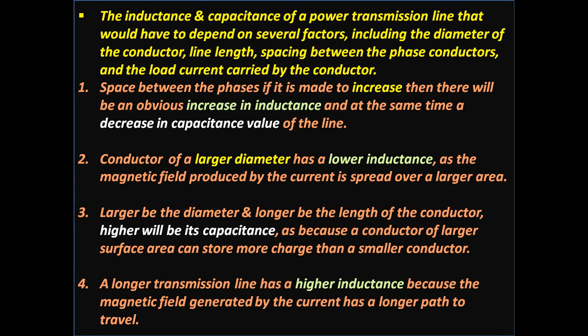Number two, a conductor of large diameter has a lower inductance as the magnetic field produced by the current is spread over a larger area. Number three, the larger the diameter and the longer the length of the conductor, the higher its capacitance, because a conductor of larger surface area can store more charge than a smaller conductor. A longer transmission line has a higher inductance because the magnetic field generated by the current has a longer path to travel. These four are much more important.